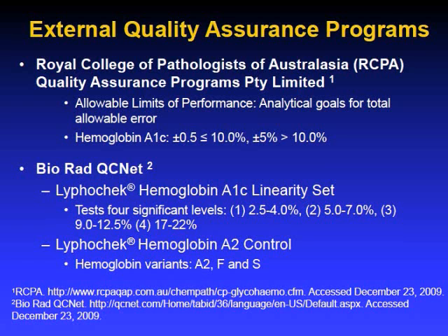In a recent publication released in November 2009 in the journal Clinical Chemistry, Lunters, Westra, and authors showed that only 2 out of 8 hemoglobin A1c point-of-care instruments met the generally accepted analytical performance criteria. The 2 instruments that met the acceptance criteria were Afinion and DCA Vantage, for having a total CV of less than 3% in the clinically relevant range.